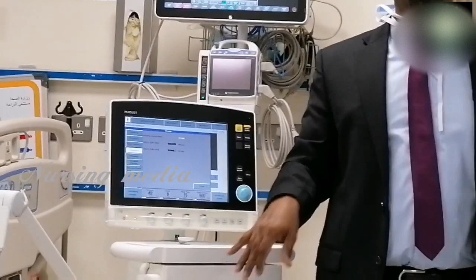According to the FDA and medical equipment management certification, it should be kept 365 by 7, even when not using it. From our side we say this, but you follow the hospital on this. What we say is 24 by 7 it has to be connected to the mains power. We are not saving the batteries, we want to save the life. Imagine it's not properly charged. One day somebody forgot to charge, you have an emergency, there's an emergency shutdown. What will you do?